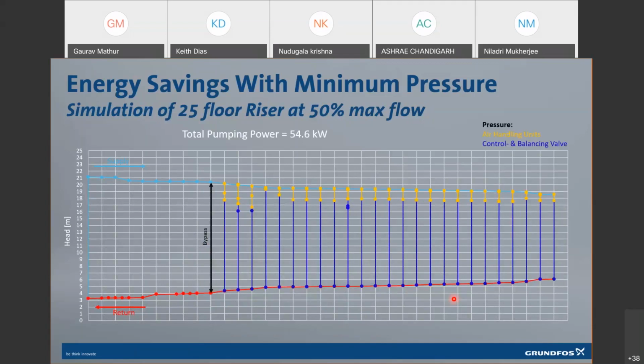Now, we discussed the minimum pressure part and how a traditional system pressurizes the entire circuit. If you look at this light blue line, this is the pressure which is created by a conventional variable primary system. And do you see the orange lines? These are nothing but the actual requirement. So you have to run the pump to ensure that we are able to take the water till the farthest point.